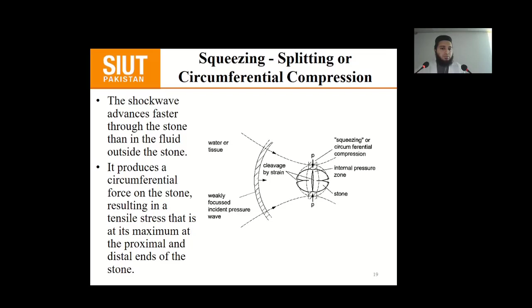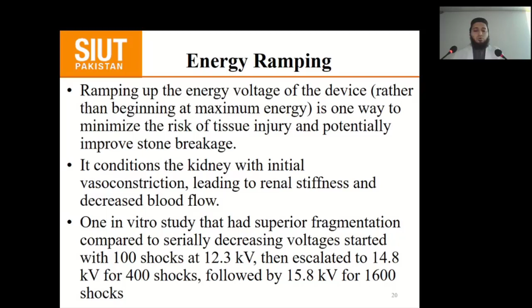So, energy ramping. What is ramping? Ramping is when we increase the energy slowly and gradually so as to achieve the maximum stone-free rate and to decrease perirenal hematomas. Ramping up the energy voltage of the device rather than beginning at the maximum energy is one way to minimize the risk of tissue injury and potentially improve stone breakage. It conditions the kidney with initial vasoconstriction, leading to renal stiffness and decreased blood flow. One in vitro study that had superior fragmentation compared to serially decreasing voltages started with 100 shocks at 12.3 kilovolts, then escalated to 14.8 kilovolts for 400 shocks, followed by 15.8 kilovolts for 1600 shocks.